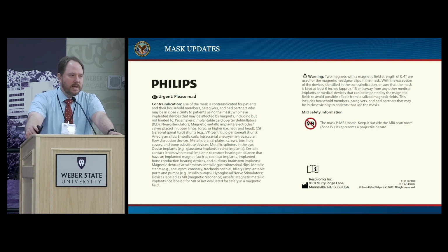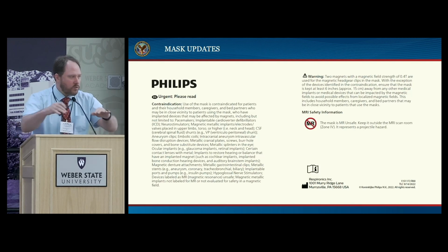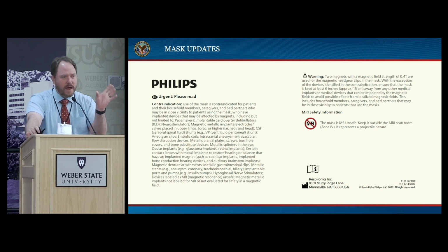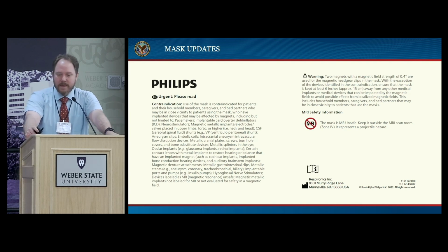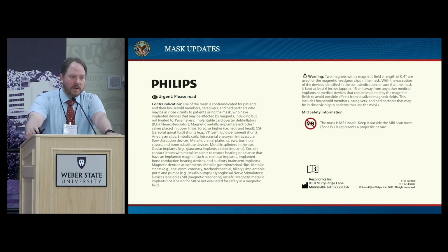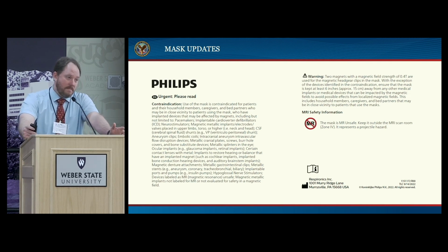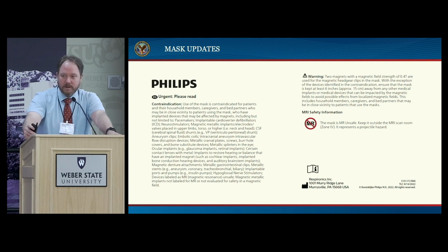What they should be doing is contacting their equipment company, and the manufacturer has set up what they call a crosswalk, where if this is the mask you're using, you can switch to this one that's very similar but doesn't have magnets. The new labeling you can see is very cumbersome, but it has been adjusted, it's been added to the new packaging, and these masks are back in circulation. But you should be aware that if your patient has a pacemaker or something and they use CPAP, you should probably make sure that they're not using a mask that has magnets, as it may put the pacemaker into the default mode or interfere with it in other ways.